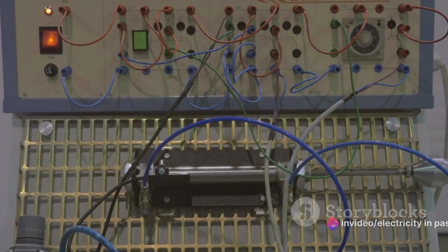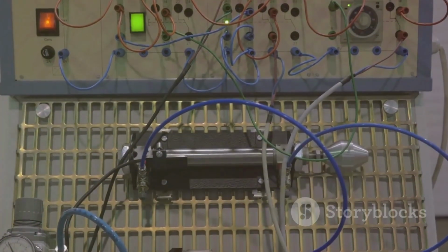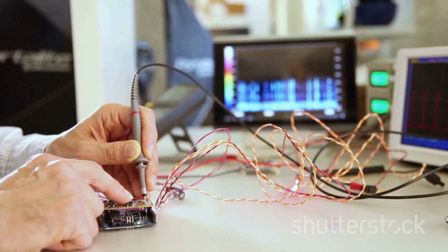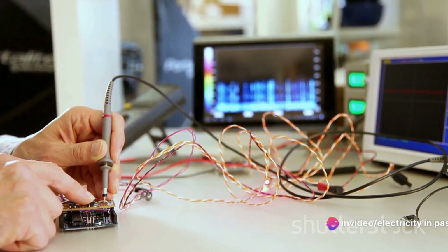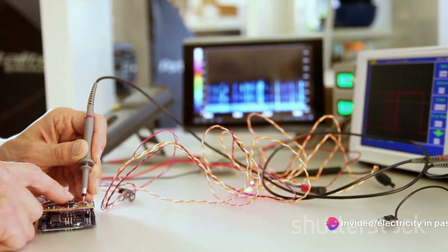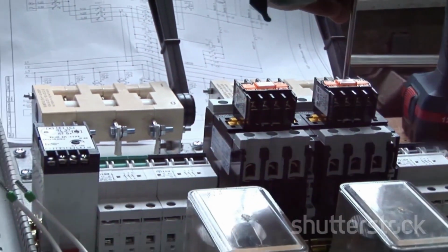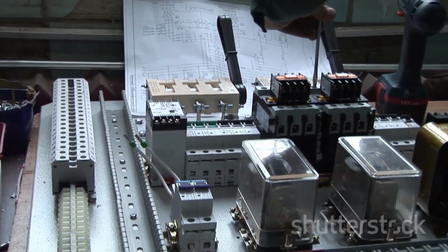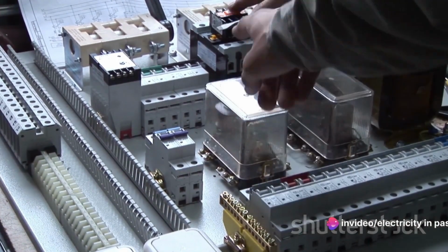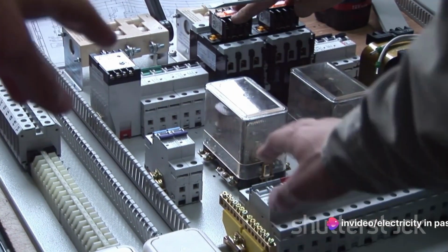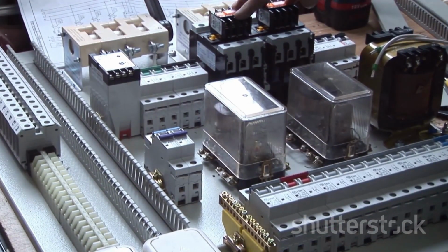Now, let's talk about how it all comes together. When the switch is turned on, the motor is directly connected to the power supply. This is why it's called a direct online circuit. The motor starts up at full speed almost instantaneously. It's a bit like jumping into a cold pool. There's no gradual acclimation, it's 0 to full power in an instant. However, this sudden rush of power can cause a high inrush current, which is typically 6 to 10 times the motor's full load current. This can lead to mechanical stress on the motor and electrical stress on the power lines, which is why DOL circuits are generally used for smaller motors.